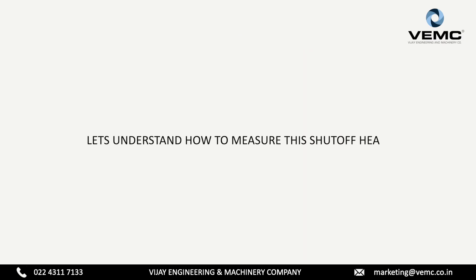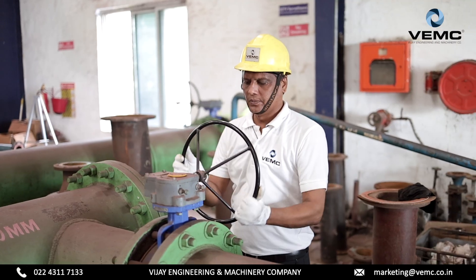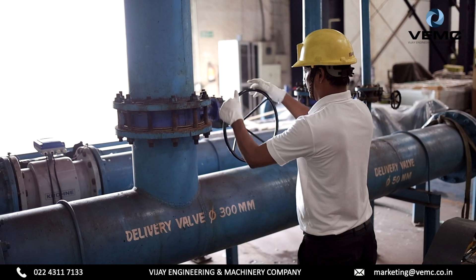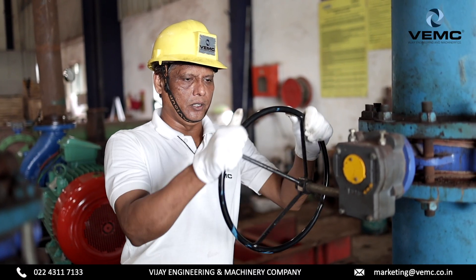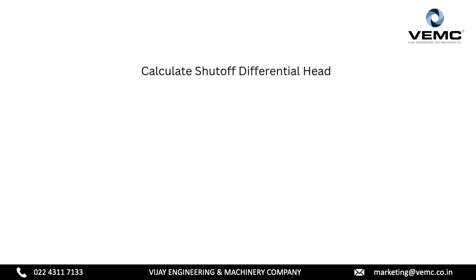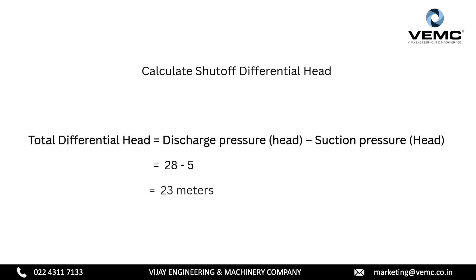Let's understand how to measure this shut off head. Start the pump and ensure that the suction valve is fully open. Observe and record the suction pressure from the pressure gauge. Next, close the delivery valve completely to 100% and maintain this position for 30 seconds only. Then note the discharge pressure as indicated on the discharge pressure gauge. Calculate shut off differential head equals discharge pressure minus suction pressure, that is 28 minus 5. Therefore, shut off differential head is 23 meters.